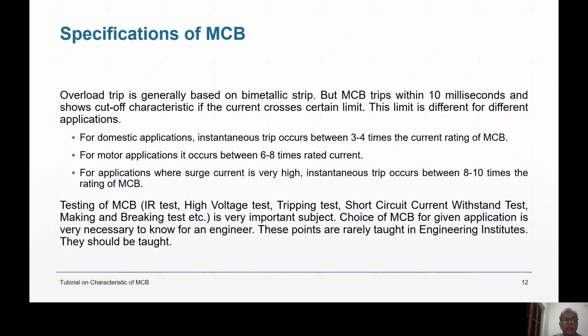Overload trip is generally based on bimetallic strip, as we have told, right? But at what current should it trip instantaneously? If you are using the MCB for domestic applications, it should trip somewhere between 3 to 4 times the rated current. That means if I'm buying a 2 ampere MCB, 2 into 3, 6 or 8 amperes, it will trip instantaneously.